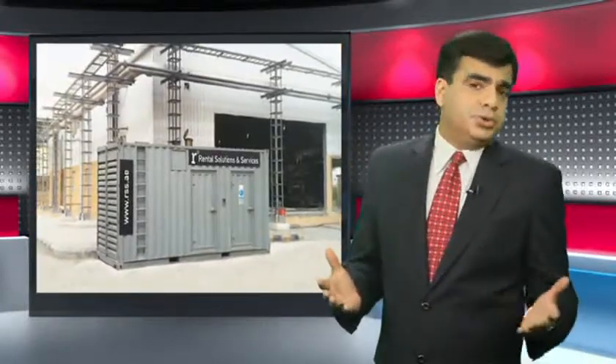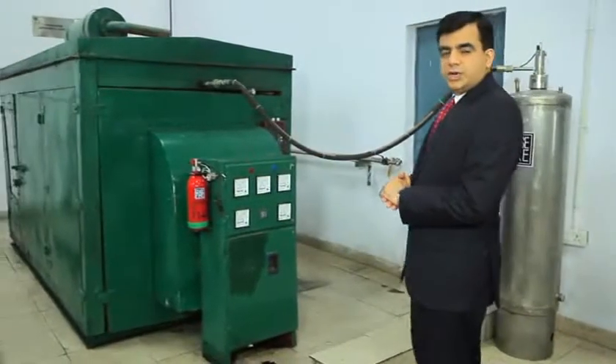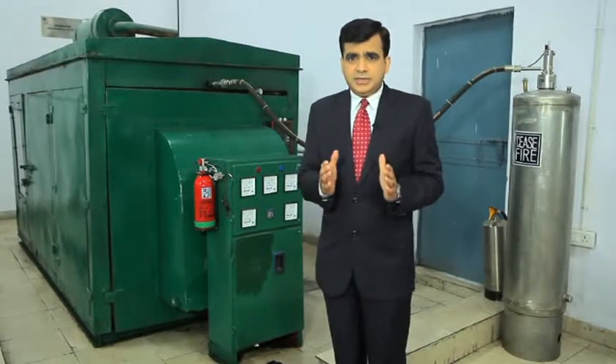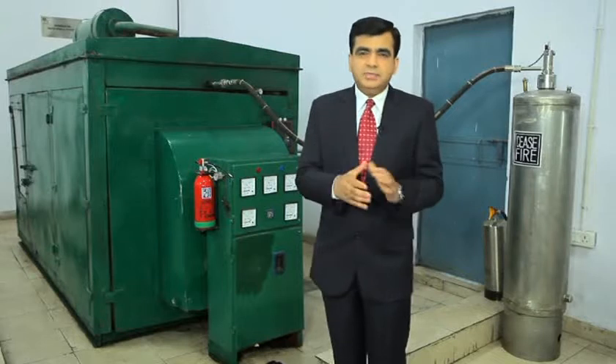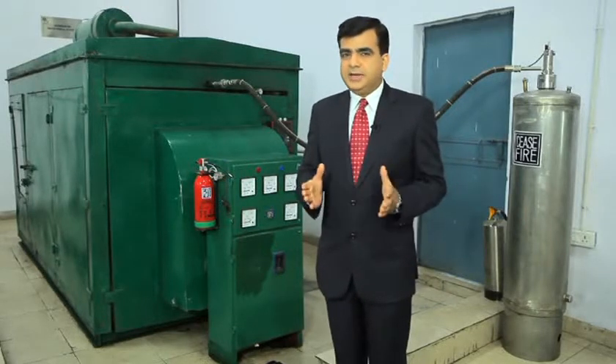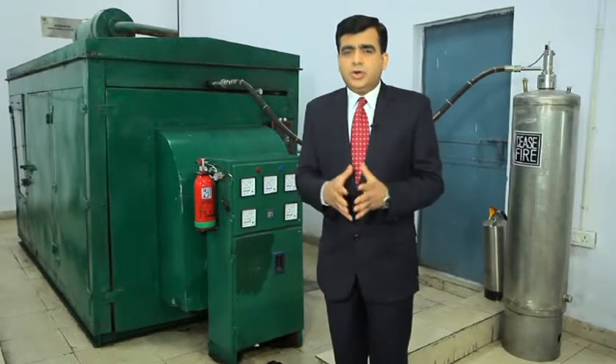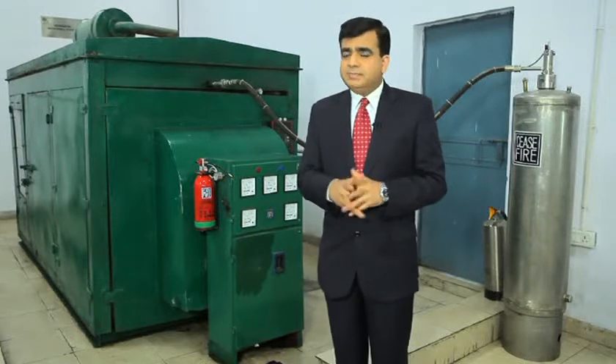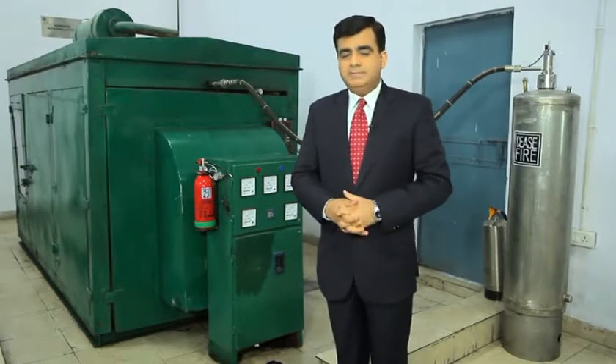Unfortunately, fires in generators can go undetected because they're often located at a remote area. The combination of inflammable materials and the remote location can lead to a dangerous situation. The fire that rages on and results in an explosion could even spread to neighboring areas. The need then is for an extinguishing system that works automatically and is extremely effective. That's where the Ceasefire Generator Auto-Quell System comes in. An integrated enclosed environment system, it combines water mist and clean agent suppression technology, and it actuates automatically. Not only is water mist effective against oil and gasoline-based fires, it's also eco-friendly and has zero ozone-depleting properties.